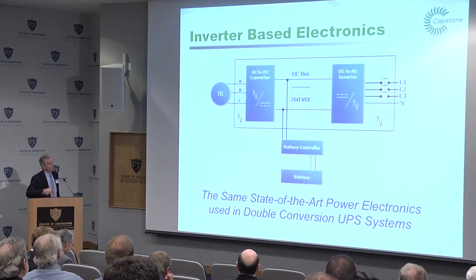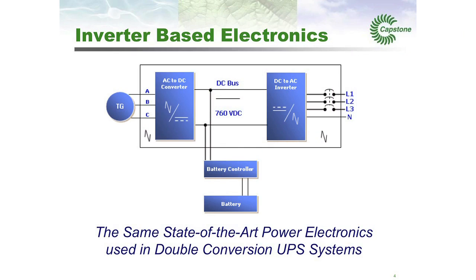We also have a version with a battery backup for starting. If you're standalone with no grid at all, you need some energy to start the system, so we take that from a battery through another converter — in this case DC to DC — to provide power to start the turbine. We also use that to level load, since turbines don't like to change power output very rapidly. So we use the battery as a source and sink to make sure the output on the utility side, the user side, remains very stable in terms of frequency and voltage.